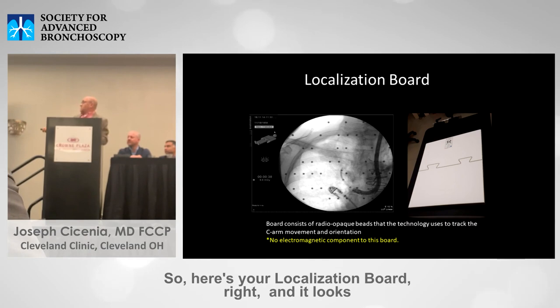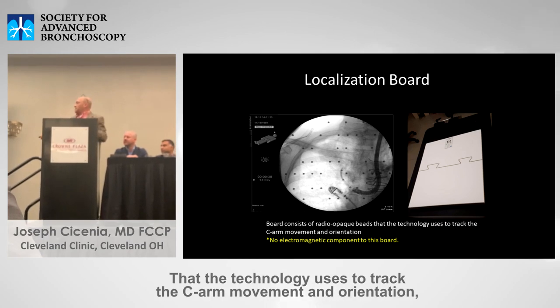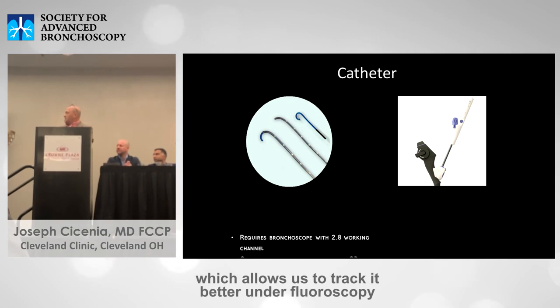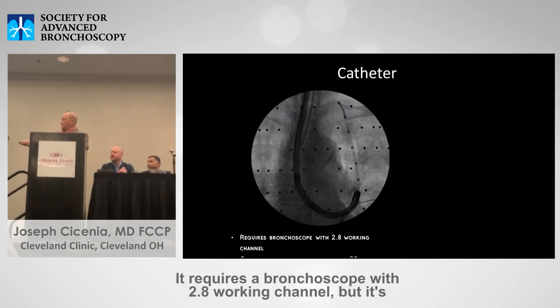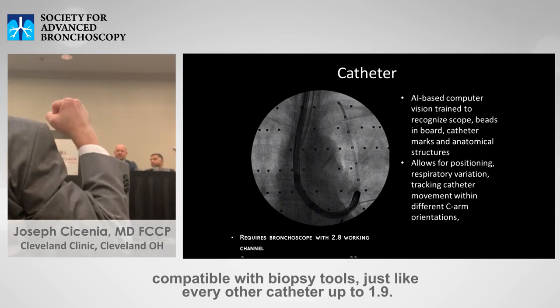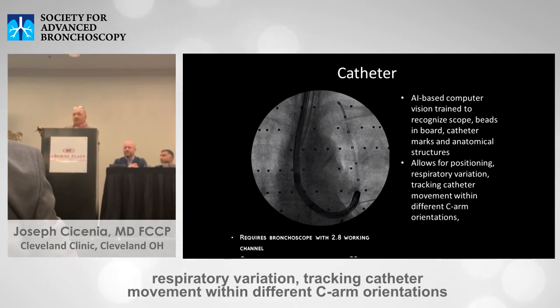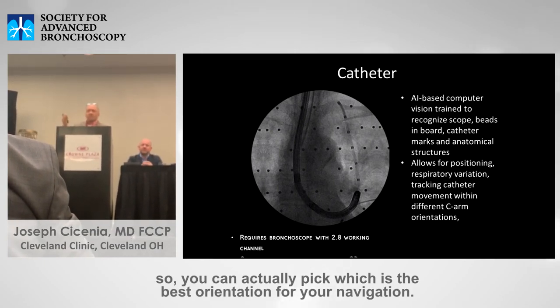Here's your localization board — it looks a little like localization boards we've already used. It consists of radio-opaque beads, which is the technology used to track C-arm movement and orientation. There's no electromagnetic component to this board. There's a catheter with little radio-opaque beads that allows us to track it better. It's a curved catheter requiring a 2.8 working channel, compatible with biopsy tools. This AI computer vision is trained to recognize the scope, the beads, the board, the catheter marks, and anatomical structures, allowing for positioning, respiratory variation tracking, and catheter movement within different C-arm orientations.